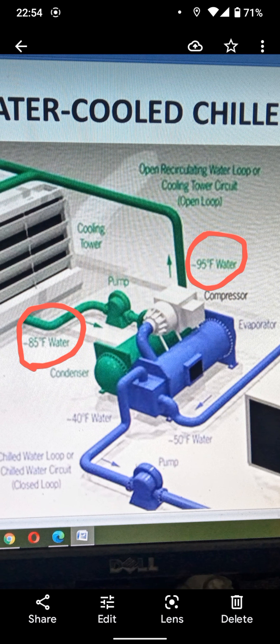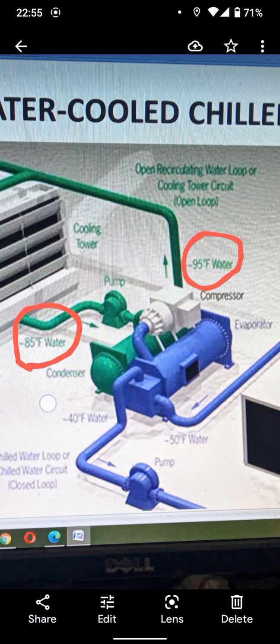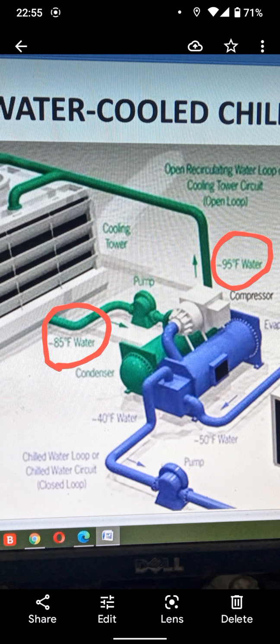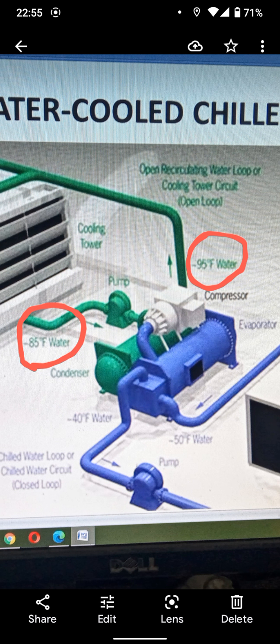Normally, people who work on centrifugal chillers know the condenser pressure and temperature increase. The refrigerant flows back, pressing in the reverse direction through the impeller. When the surge occurs, the chiller vibrates violently, and refrigerant passes through the impeller from the condenser to the cooler evaporator. When this surging occurs, the amperes also fluctuate. Surging is not good for a centrifugal chiller; more surging may damage your machine.